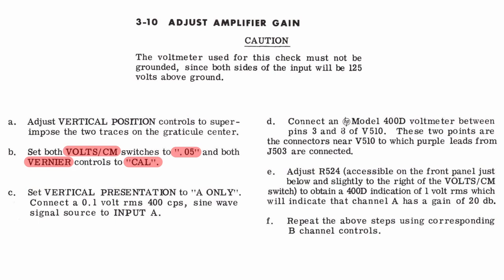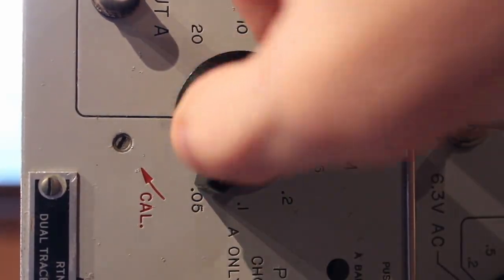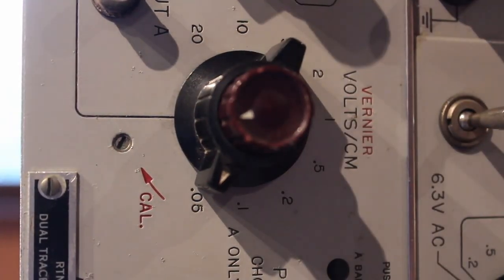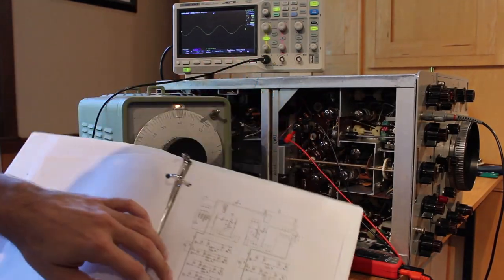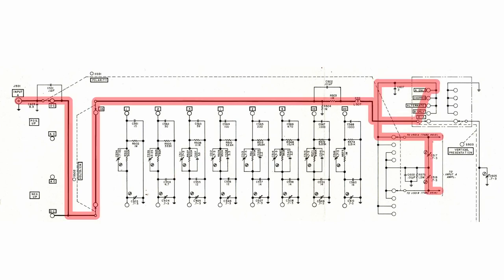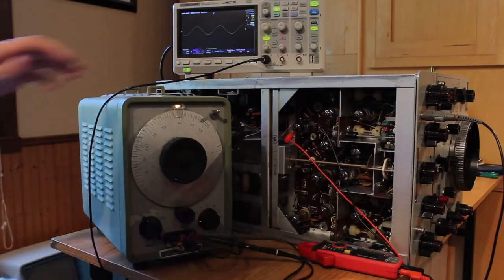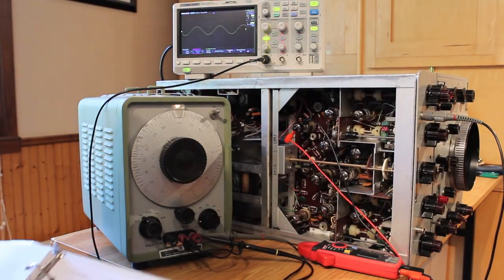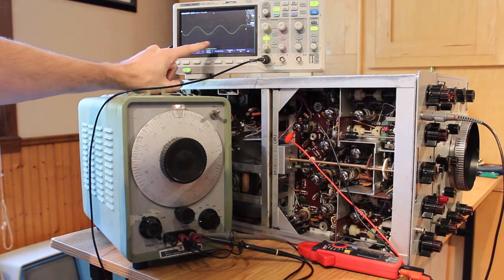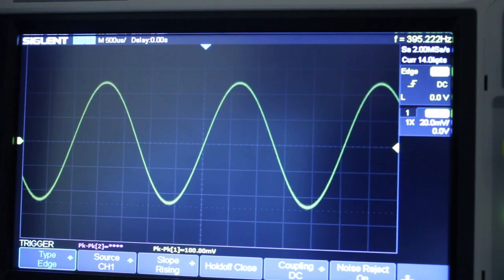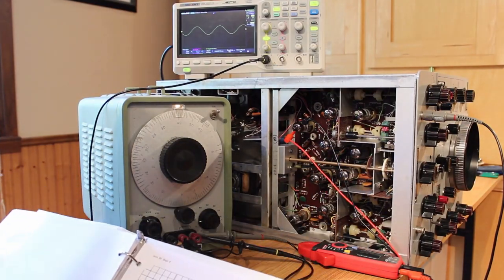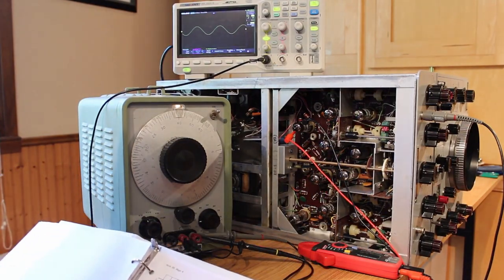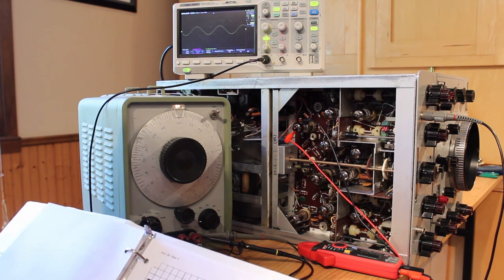So it says we had to set both volts per centimeter switches to 0.05 and both vernier controls to CAL. Now the reason that we set it to 0.05 is if we skip ahead and look at this page right here, we can see that when it's set in 0.05, it essentially just bypasses all of the attenuating circuits that are in the switch. The next one is to set vertical presentation to A only, and then we want to connect the 0.1 volt RMS 400 CPS sine wave signal source to input A. And that's where this big guy comes in, this little HP 200 CD. And you can see up here, I've got it putting out a 100 millivolt peak to peak sine wave at 400 hertz while we're at 393. But boom, there we go. I thought we were on the right track.